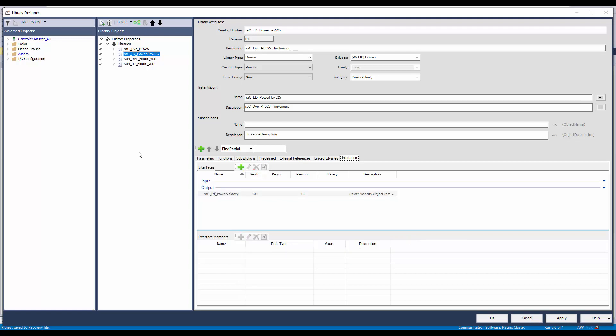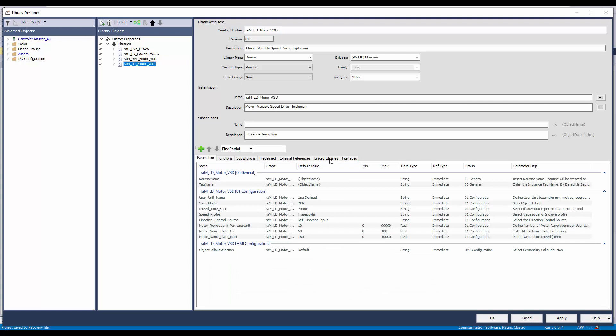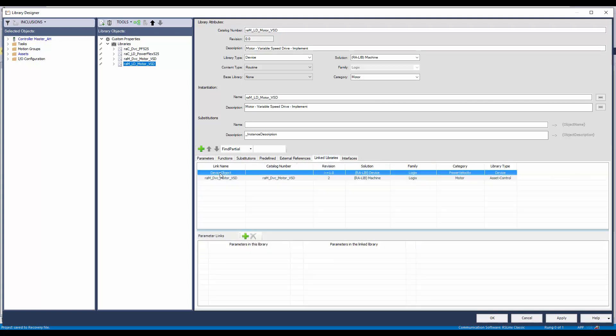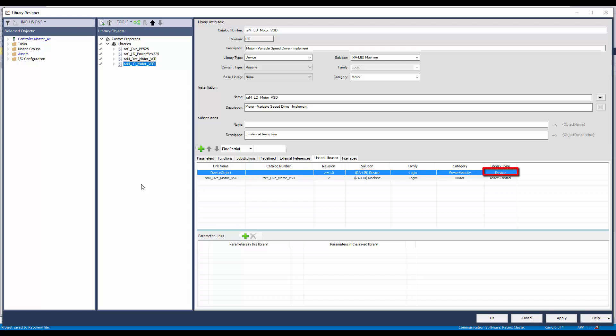Next, I will open the Motor VSD implement type object and open the link libraries. I have already added a link library for the device object. As you can see, the catalog number is empty, which means the Motor VSD object can connect to any library belonging to the device solution, device library type, and power velocity category. This gives flexibility to the user to connect to any velocity class device. This also means that similar to PowerFlex 525, all velocity class devices will need to have an output interface to pass the program name, tag name, and module name information.